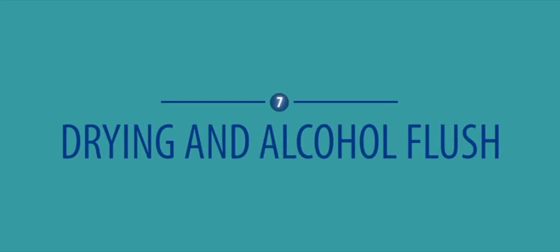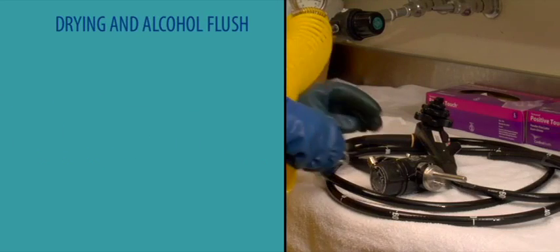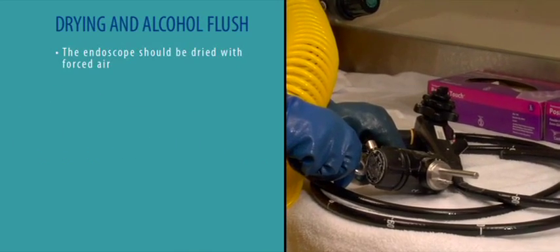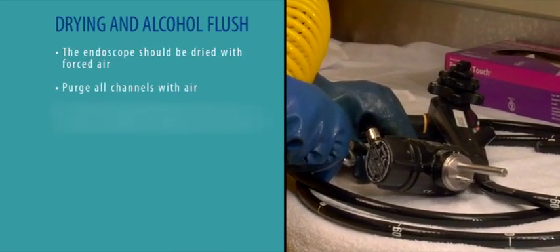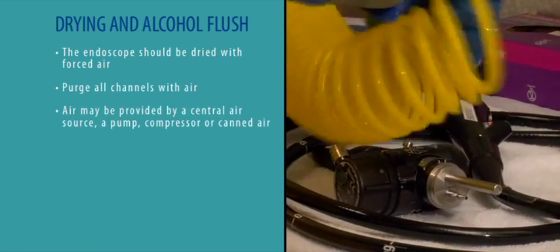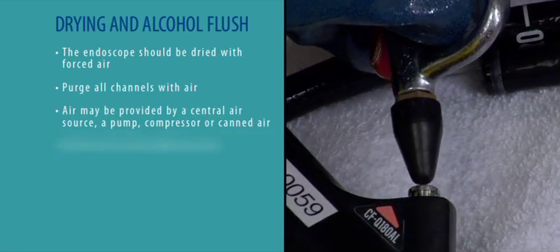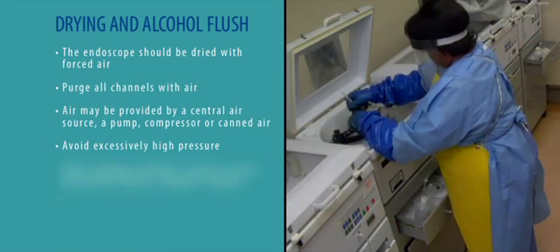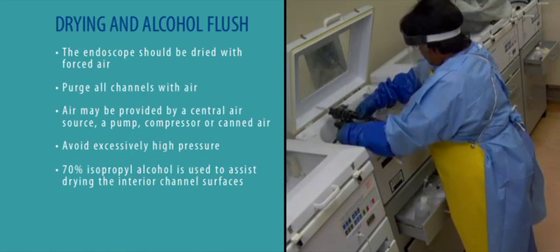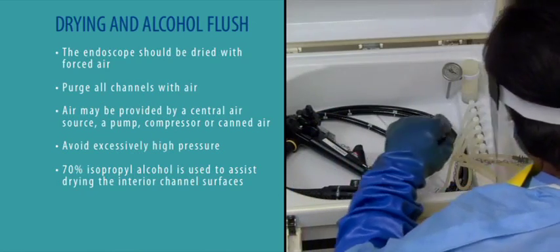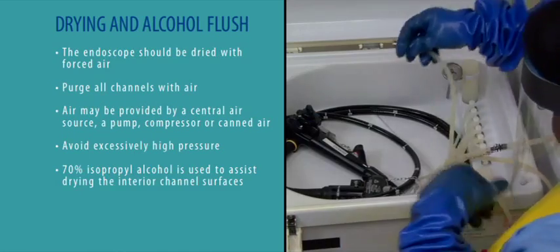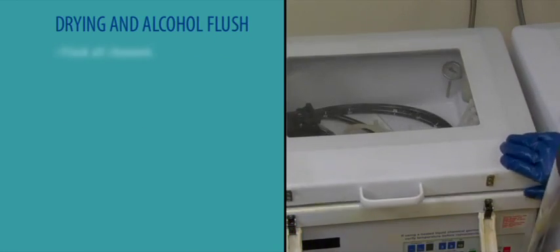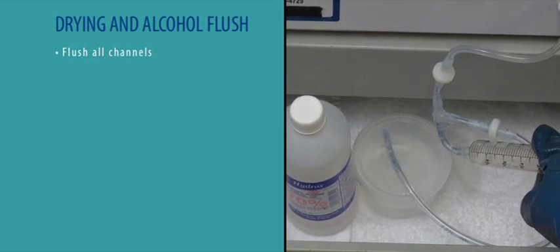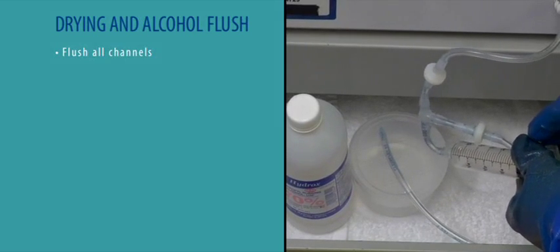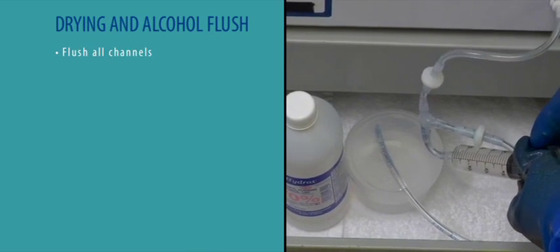7. Drying and alcohol flush. The endoscope should be dried with forced air to complete reprocessing. Purge all channels with air. Air may be provided by a central air source, a pump or compressor, or canned air. Avoid excessively high pressure. 70% isopropyl alcohol is used to assist drying the interior channel surfaces. An alcohol flush should be used even if sterile water is used for rinsing. Flush all channels, including accessory channels, with alcohol until the alcohol can be seen exiting the opposite end of each channel. Regardless of the AER, the ERCP channel should be flushed with alcohol and manually dried.